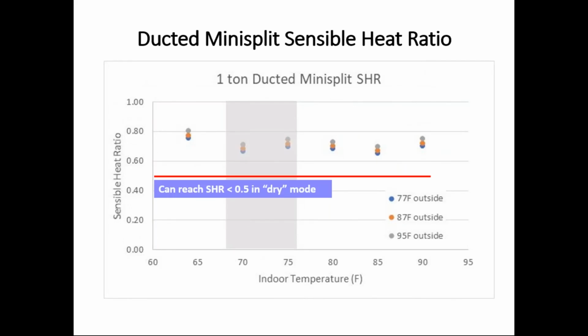Sensible heat ratio in conventional air conditioning operation is somewhere around 75%, but in this dry mode, it can drop down to about 50%. And so, for example, in my house, when we start getting up above 60, 65%, I'll put the ductless mini split into dry mode or dehum mode for about 8 hours. And then maybe once a week when we're in the thick of things in July and August in the house. That's enough to bring it down to maybe upper 50s, and then it just coasts up over the next week or so to maybe lower 60%, depending on the weather and the activity. But it's a very easy thing to do and gives us the ability to control the moisture nicely.